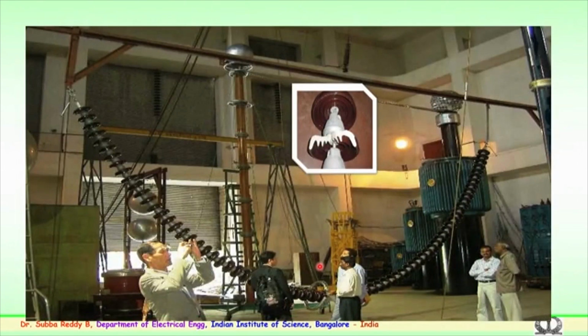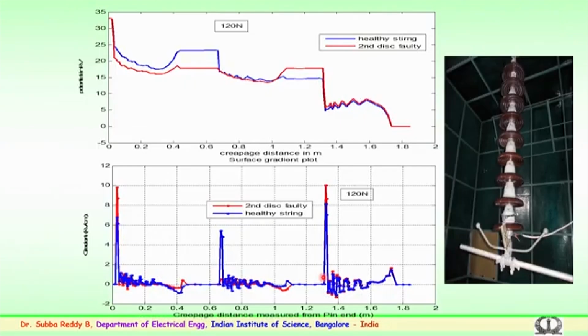Several experiments and theoretical simulations have been conducted with the developed method at the laboratory. We have tried to see this using the surface charge simulation method. This is one particular experimental simulation which has been carried out for 3 discs in a string. So, with 3 discs, 33 kV is the potential at the line end, the second will be at a potential somewhere around 20 to 23 kV, and the third will be around 11 or 13 kV.